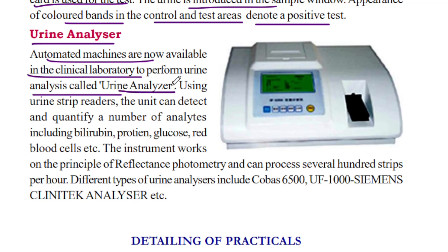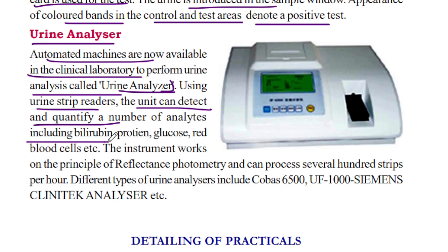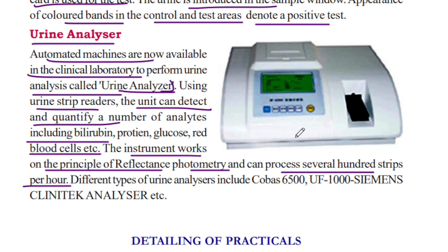Automated urine strip readers use urine strip technology. The unit can detect and quantify a number of analytes, including bilirubin, protein, glucose, and red blood cells. The instrument works on the principle of reflectance photometry and can process several hundred strips per hour.